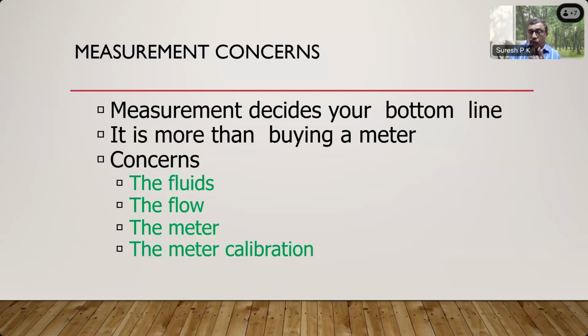And the flow, steady flow. If it is not steady, then you are going to get affected. So the fluids affect the flow measurement accuracy. The flow affects the flow measurement accuracy. The meter characteristics affect the flow meter accuracy. See, you don't need the most accurate meter for all measurements. It depends on your measurement accuracy requirement. Sometimes you need only a DP meter. Sometimes you need only a vortex meter. Sometimes you may have to go for a mass flow meter, where the cost of the fluid involved or the cost of the process involved in the measurement decides the meter.